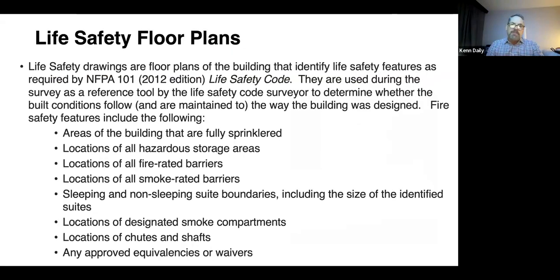The first thing that's really come to light in the past several months, or maybe a couple of years since we've had a new survey, kind of restart the survey since the pandemic, is that for the drawings of our buildings, the survey agencies are really pressing today to have a drawing that's referred to as a life safety floor plan. It's not good enough to take a basic floor plan of your building and have some squares on it that represent patient rooms and offices and maybe the dining room, but all those have to be labeled. And then a life safety drawing is things like showing the surveyor where your pull stations are, where your vertical openings are, where your fire extinguishers are, where all your smoke and fire barriers are located.